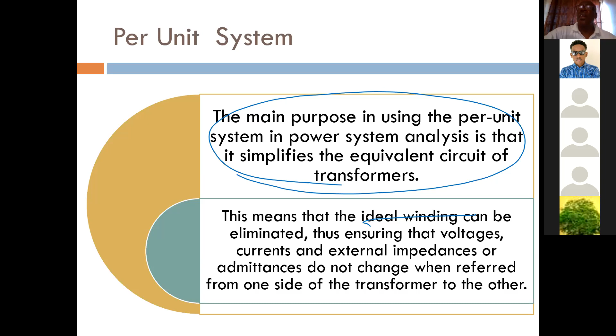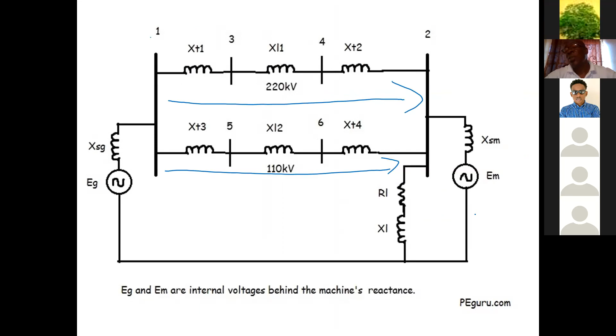So the per unit value would remain the same whether you are going from secondary or primary. That is the beauty of this system, because it simplifies the transformer and gives it a simple per unit reactance value. Then with that per unit reactance value, you'd have a simple network, not quite series-parallel since you have two sources, but one you could use your standard network analysis tools to solve.